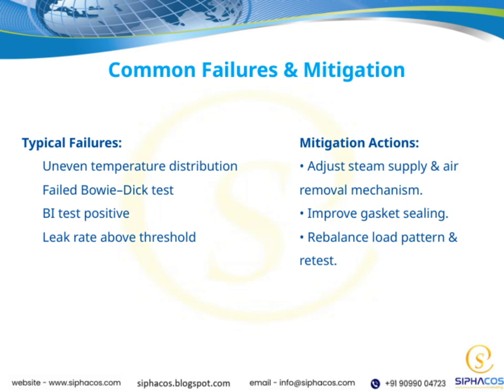Improving gasket sealing is also crucial, because a good seal prevents leaks and maintains the integrity of the sterilizer environment. Lastly, rebalance the load pattern and retest. This step ensures that everything is evenly distributed, which helps achieve consistent sterilization results.